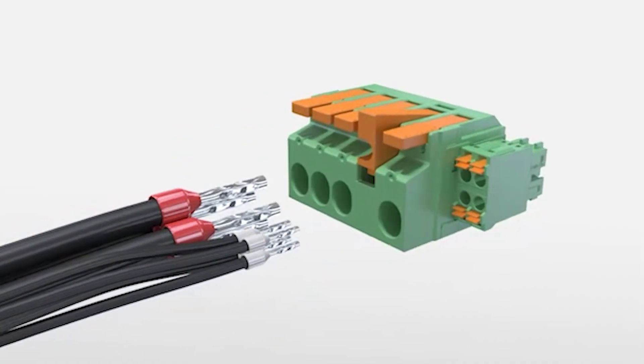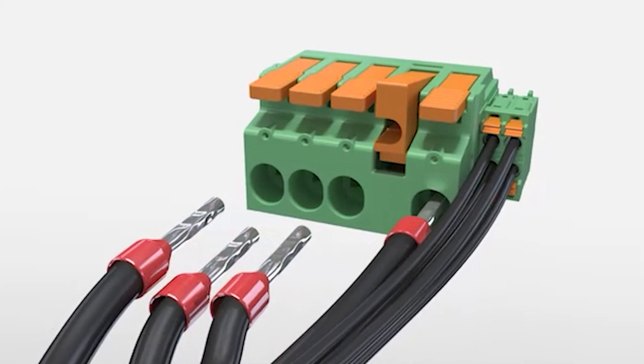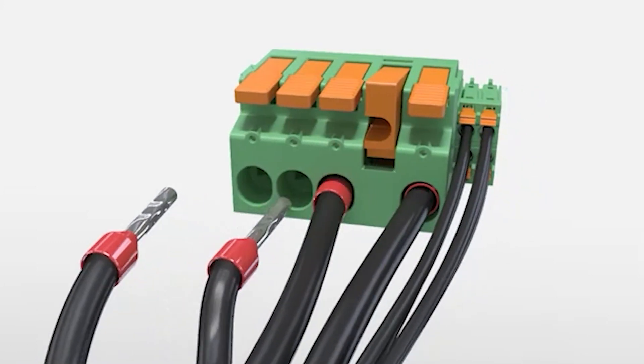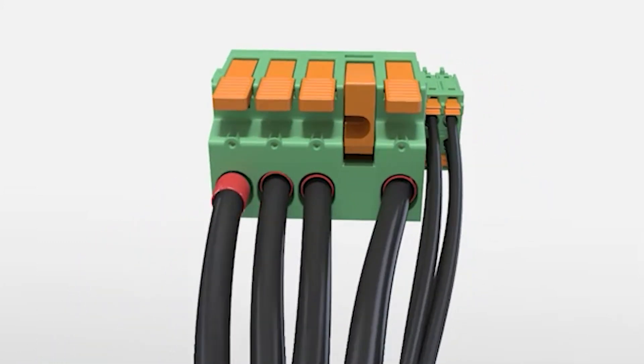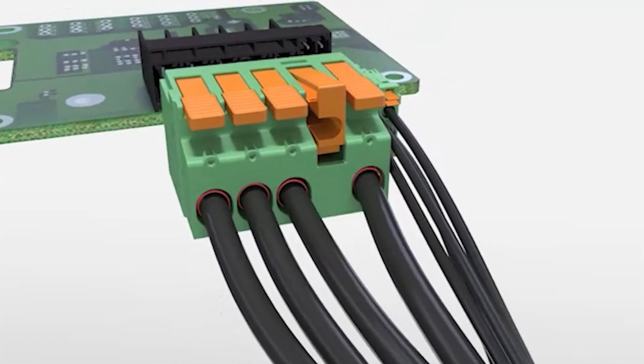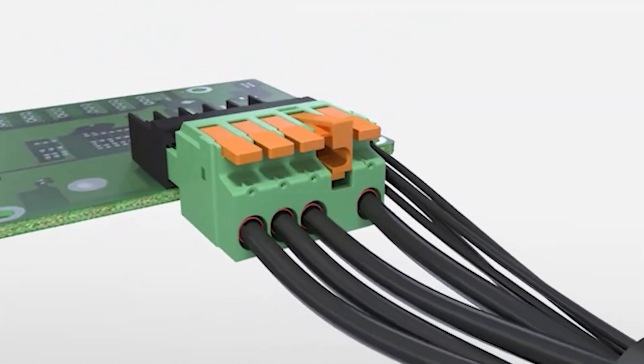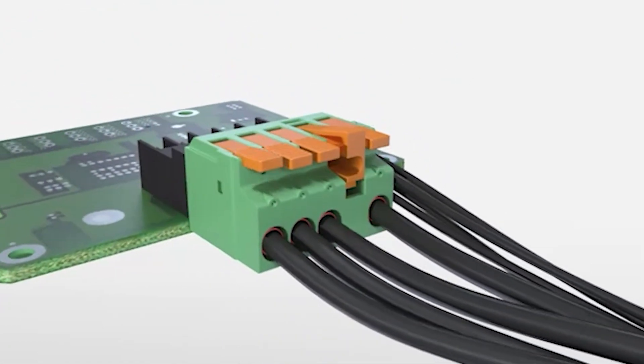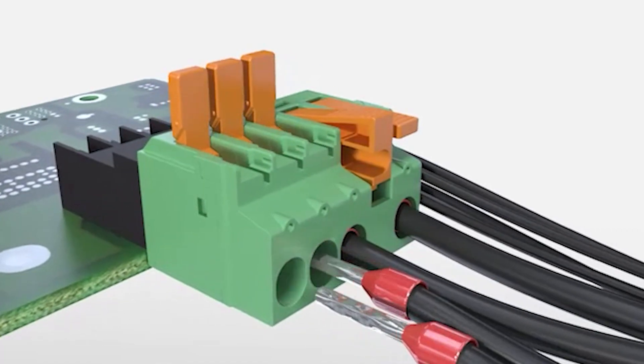There are three trends to consider when choosing a connector for motor and drive or power conversion applications. First, the connection of the wire needs to be simple and intuitive without the need for special tools. Levered spring connections are ideal in this type of product since they are easy to use and provide visual and audible feedback when the wire is terminated correctly.